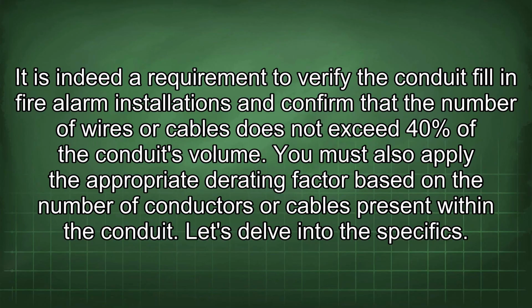It is indeed a requirement to verify the conduit fill in fire alarm installations and confirm that the number of wires or cables does not exceed 40% of the conduit's volume. You must also apply the appropriate derating factor based on the number of conductors or cables present within the conduit. Let's delve into the specifics.